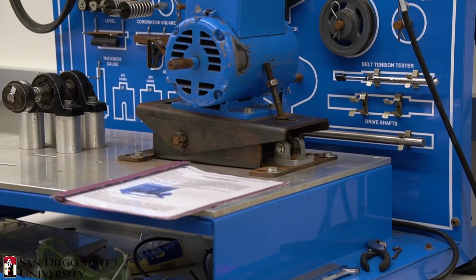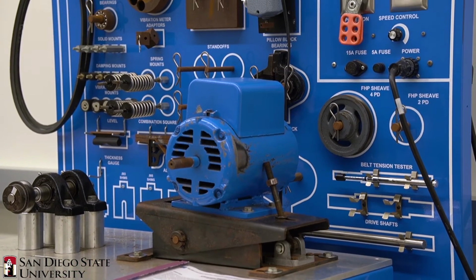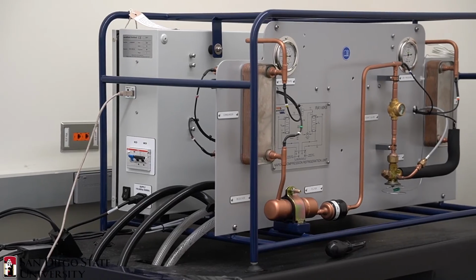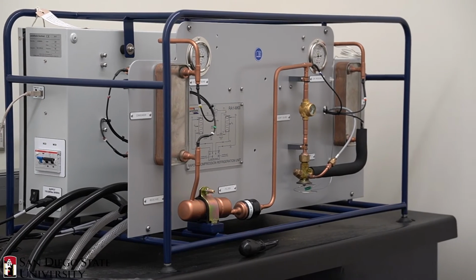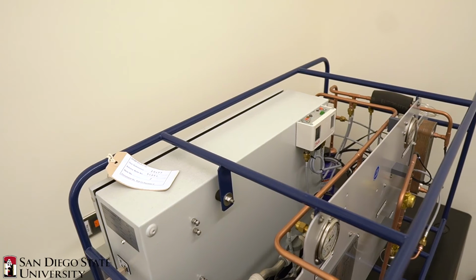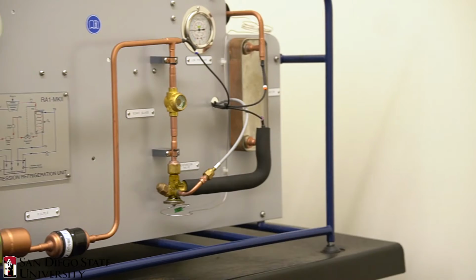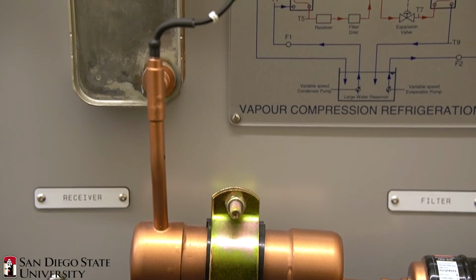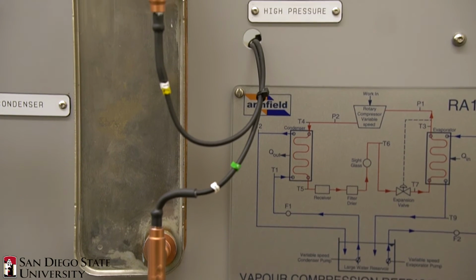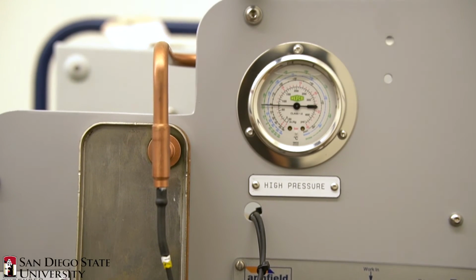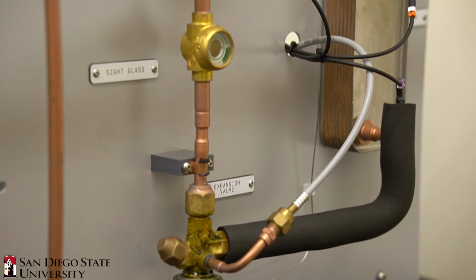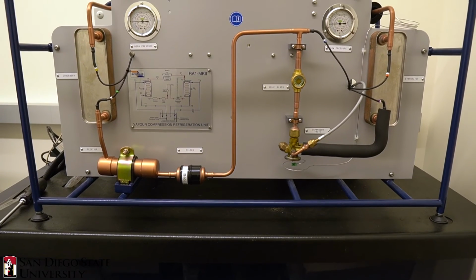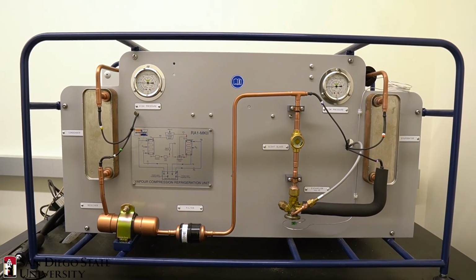Vertical and horizontal readings are made to detect worn or stretched belts, and axial readings are used to detect belt or sheave misalignments. The armfield RA1 refrigeration unit is used to demonstrate the important features and operation of a vapor compression refrigeration system. Students analyze the combined process of compression, condensation, expansion, and evaporation during the experiment. The expansion valve is varied to control the liquid flow for different loading conditions, and parameters such as temperature and pressure are recorded to determine the system performance. The results are logged by students, and they compare multiple graphs to identify the optimal settings.